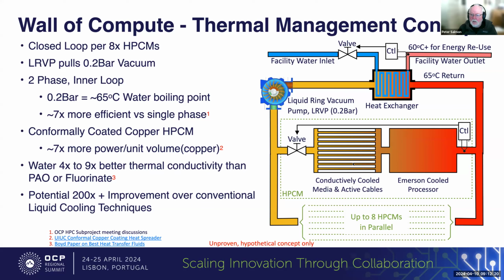Times 8. And then we would have a valve on the inlet with a temperature monitor on the outlet, making sure that depending on what power we're burning in here, we always get a 65 degrees C return temperature. So this valve opens and closes to reduce or increase the flow as needed, and you do that 8 times - so we've got one control loop going on here, 8 times.